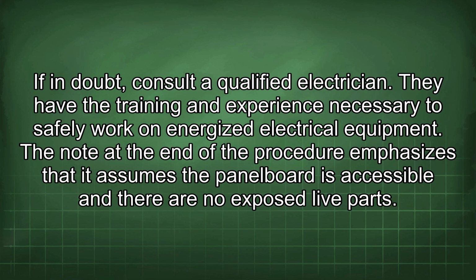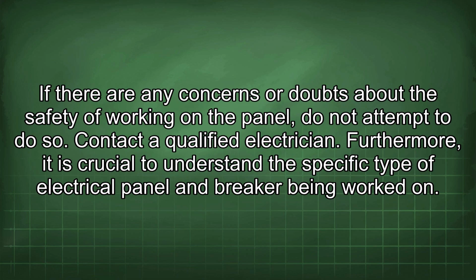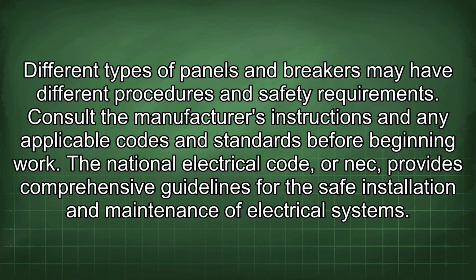The note at the end of the procedure emphasizes that it assumes the panel board is accessible and there are no exposed live parts. If there are any concerns or doubts about the safety of working on the panel, do not attempt to do so. Contact a qualified electrician. Furthermore, it is crucial to understand the specific type of electrical panel and breaker being worked on. Different types of panels and breakers may have different procedures and safety requirements. Consult the manufacturer's instructions and any applicable codes and standards before beginning work.